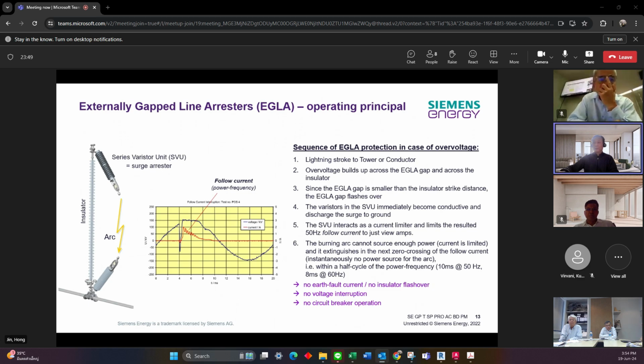So this is how the EGLA works. As mentioned before, if we have received a lightning strike, the lightning overvoltage will travel to the insulator and produce the overvoltage from both ends of the insulator. In such a case, the air gap will be sparked over, and then the surge arrester becomes active. The discharge current will go from one surge arrester through the arcing to the other one.